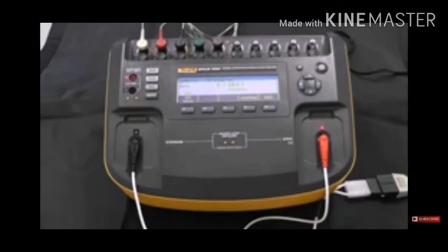I did not have to tell Impulse 7000 what to look for. It told me what it measured and what it saw based on the energy delivery. So that's kind of important. It tells you what it sees. If it was a more modern defibrillator, or an AED, it would have shown us biphasic.